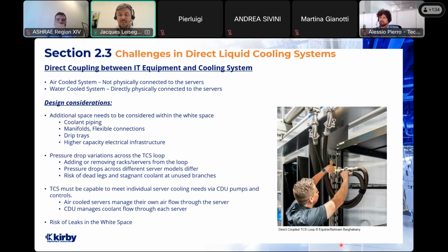In an air-cooled system, if you remove racks or remove servers, that has very little impact to the system, and you can manage that with adding blanking plates to manage your airflow. But within a liquid-cooled system, removing a rack will have a more significant impact. That will impact the pressure drop across the loop and could cause an imbalance, a hydraulic imbalance of that system. Also, if you have different servers and different racks or different server models within your racks, your hydraulic pressure profile across different server models changes.